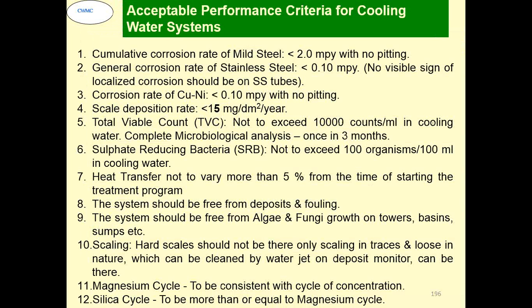Cumulative corrosion rate of mild steel in a normal cooling water system should be less than 2 mpy with no pitting. General corrosion rate of stainless steel less than 0.1 mpy with no visible sign of localized corrosion on the SS tubes. Corrosion rate of copper nickel less than 0.1. Same is applicable for brass also. Scale deposition less than 15 milligram per decimeter square per year. Total viable count not to exceed 10,000 counts per ml in cooling water. Complete microbiological analysis should be carried out once in 3 months. Sulfate reducing bacteria, SRB, not to exceed 100 organisms per 100 ml.